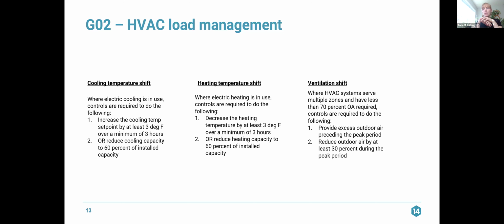Controls are required to do the following: provide excess outdoor air preceding the peak period, right? So the code developers who wrote this section recognize that you have to provide ventilation for people to breathe. And so this is where you need to do some of that shifting, right? We're going to provide excess outdoor air before the peak reduction event, and then you're going to reduce the outdoor air by at least 30% during the peak period. Okay. And that's it on that one.